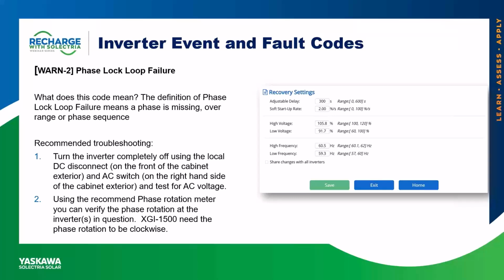Referring back to our equipment slide, under the optional category, we listed a phase rotation meter. Hooking that device up to the AC conductors in the inverter would allow you to verify the current phase rotation. And as mentioned on the slide, the XGI inverters want the rotation to be clockwise.